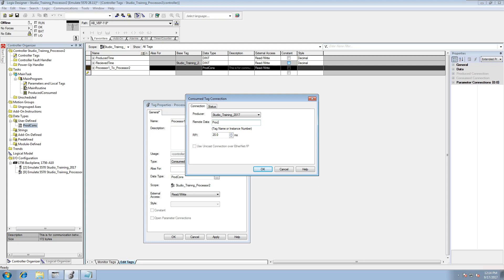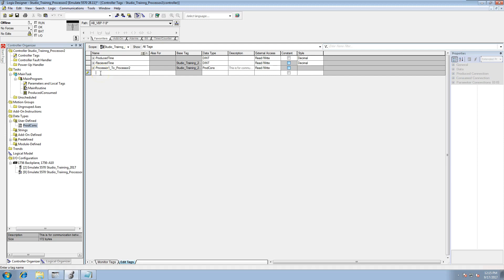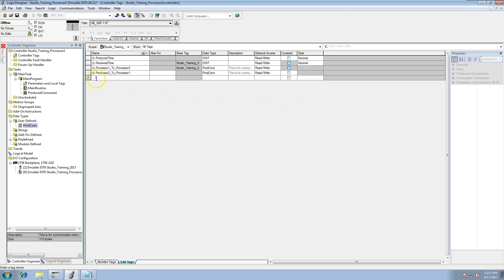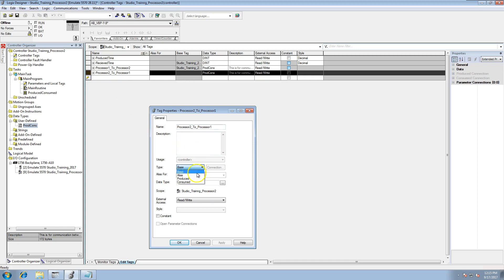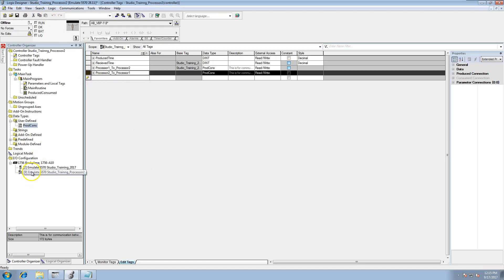We'll name this tag Processor 1 to Processor 2, and the RPI we'll keep at 20 — that's basically how fast they'll talk across the backplane. Click Apply. Then we'll make our second tag: Processor 2 to Processor 1. Use the same data type, and set this to Produced, because we're producing it from the second processor to the first.